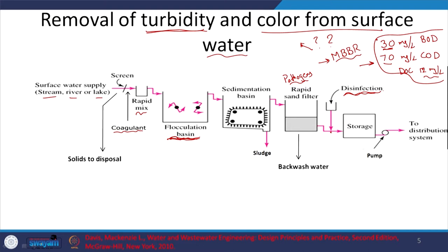You are going to disinfect the water by adding a disinfecting agent, which is typically an oxidizing compound or UV, right? Why UV? It will damage the DNA or the RNA of the pathogens. And then we are also going to ensure residual chlorine levels or residual disinfection levels, so that in the distribution system, you have chlorine that can take care of any microbial growth or re-entry into the distribution network.